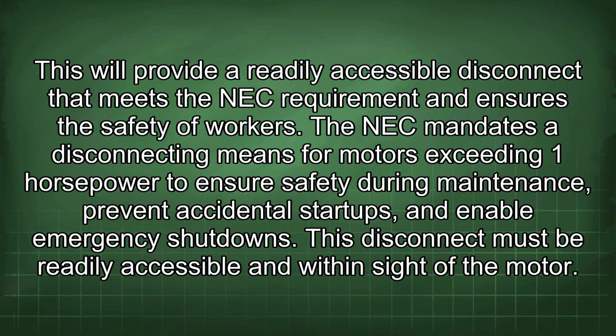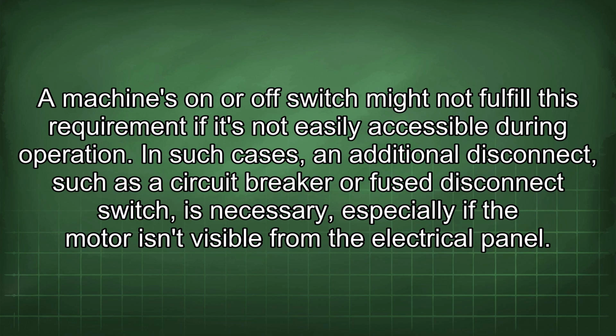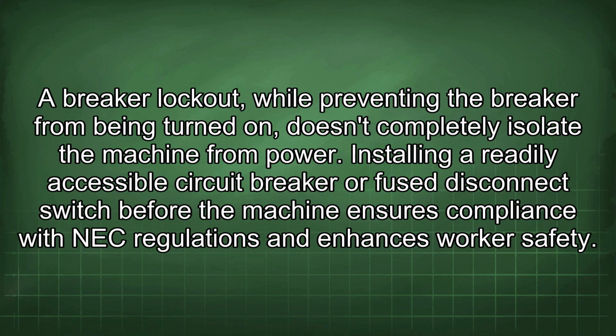The NEC mandates a disconnecting means for motors exceeding 1 horsepower to ensure safety during maintenance, prevent accidental startups, and enable emergency shutdowns. This disconnect must be readily accessible and within sight of the motor. A machine's on or off switch might not fulfill this requirement if it's not easily accessible during operation. In such cases, an additional disconnect, such as a circuit breaker or fuse disconnect switch, is necessary, especially if the motor isn't visible from the electrical panel. A breaker lockout, while preventing the breaker from being turned on, doesn't completely isolate the machine from power. Installing a readily accessible circuit breaker or fuse disconnect switch before the machine ensures compliance with NEC regulations and enhances worker safety.